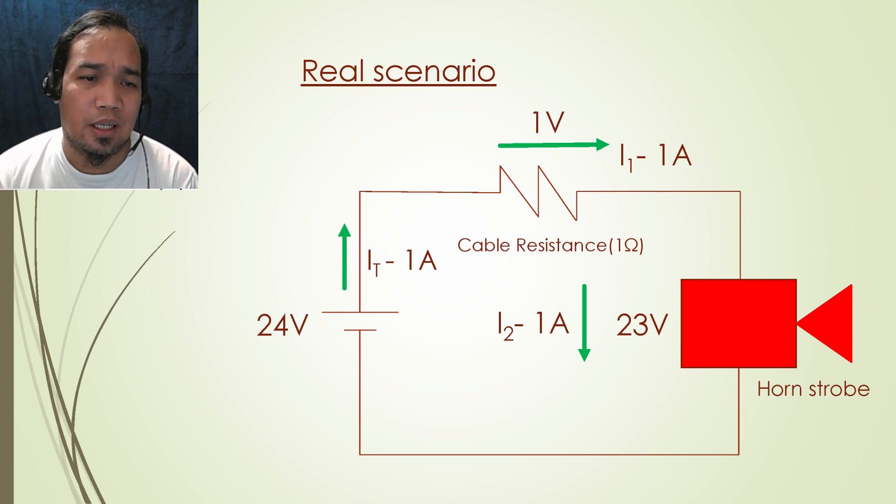But in real scenario, as shown in the illustration, some of the current is consumed by the conductor internal resistance which results in voltage drop. You will notice that only 23 volts is now received by the fire alarm horn strobe from the voltage source because of one volt voltage drop from the cable internal resistance.